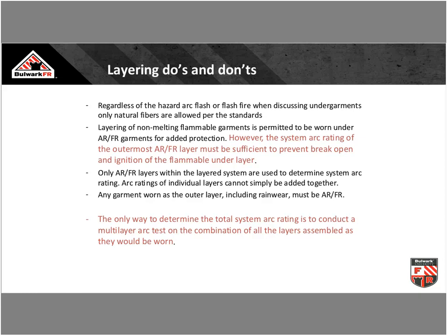Now, regardless of arc flash or flash fire, when discussing undergarments, only natural fibers are allowed per the standards. And remember, standards are our minimum baseline, we can always do better. Layering of non-melting flammable garments is permitted, meaning you can have cotton underneath your FR arc-rated outer layer, but you have to ensure that outer layer is sufficient to prevent break open.